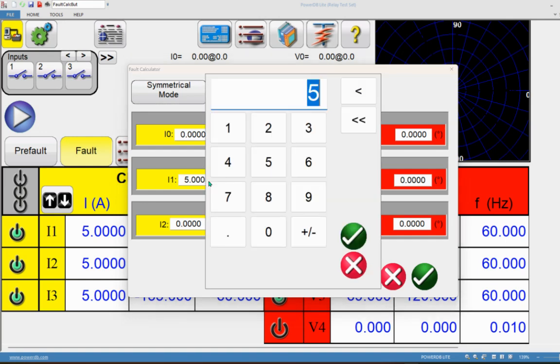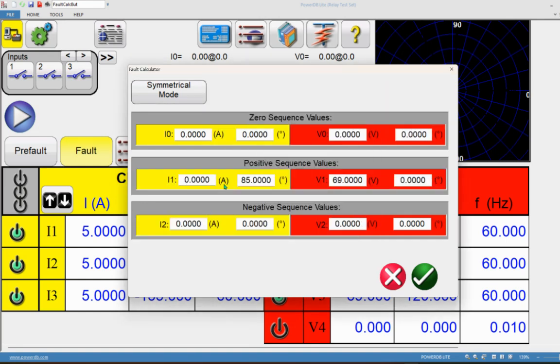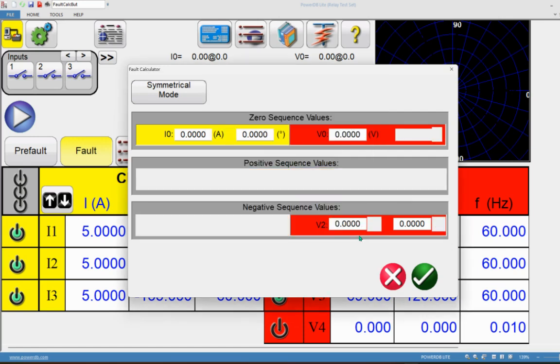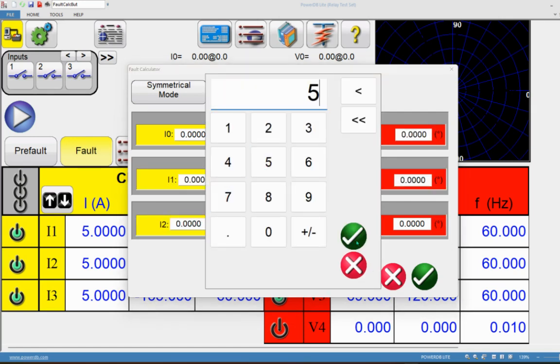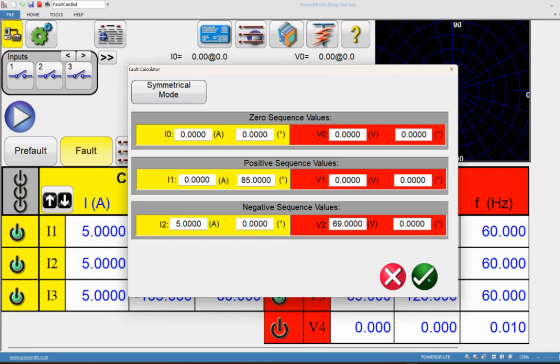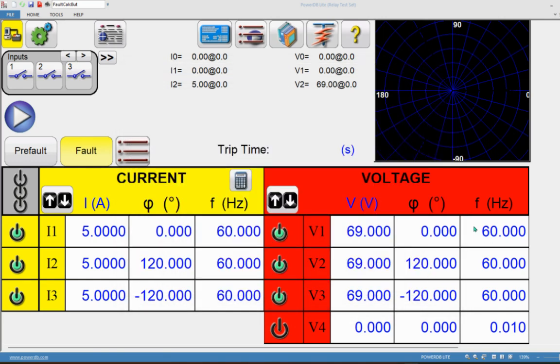Now let's define only negative sequence. Set negative sequence voltage to 69 volts and negative sequence current to 5 amps with zero degree phase angle, then click OK. On the home screen, you can see the phase angles of V2 and V3 on B and C phases changed to 120 and minus 120 degrees — this is negative sequence. Recall that in positive sequence it was minus 120 and plus 120 degrees.